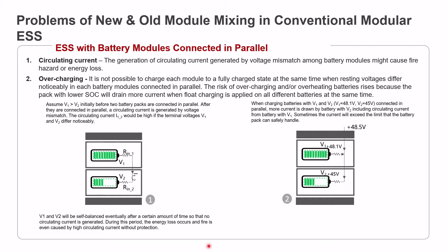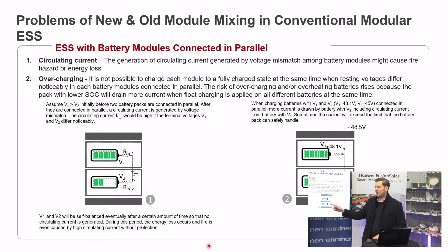A very good solution regarding the batteries is that each battery module, each battery pack, has a built-in optimizer. So for example, when you have a 10 kilowatt hour battery and after 2 years you find out it's not enough and you want to buy another one or two, you don't have to worry about the old battery packs decreasing the overall performance of the whole system. The series resistance difference doesn't matter, because the optimizer at the output will always adjust the output parameters. So one battery pack can be charged to 20%, another to 35%, another to 50% - it doesn't matter, because the output optimizer will always control the voltage and current on the main bus. So whatever happens, you can mix old modules with new modules and it will work very well.